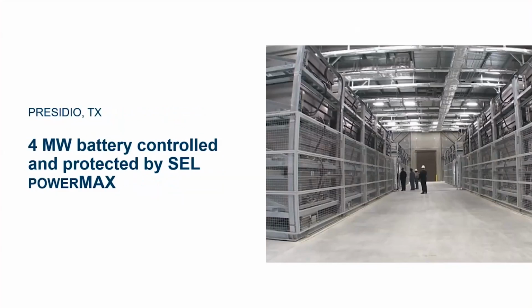Please do Google it. There's also a project you can look up. The Presidio, Texas job, circa 2008, was the largest battery in North America at the time. This battery project served a small community on the Mexico-Texas border. To solve their reliability problem, which was induced by line outages to their small community, they installed a battery, and the inverter system wasn't resilient enough, not rugged enough, couldn't supply enough current to handle the islanding events. We used SEL relays to detect the faults, isolate the microgrid, and load shed non-essential loads to make an unreliable battery-backed inverter into something very reliable. Relays doing their job, not only to island the facility correctly, but to reconnect to AEP, and when necessary, connect to the Mexico grid. Relays do the job and save the day.